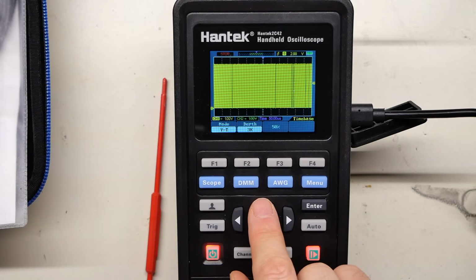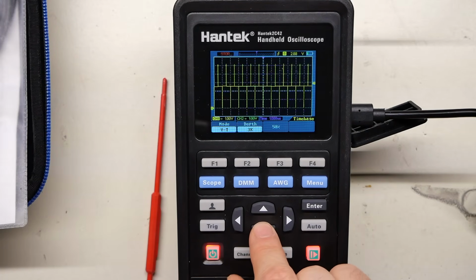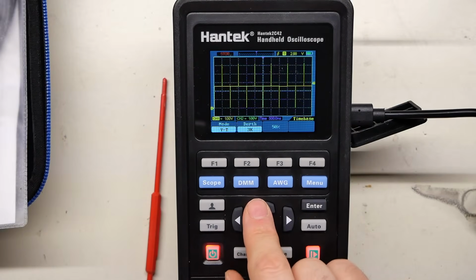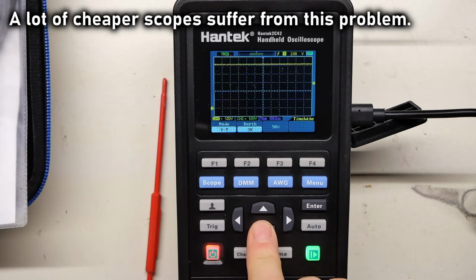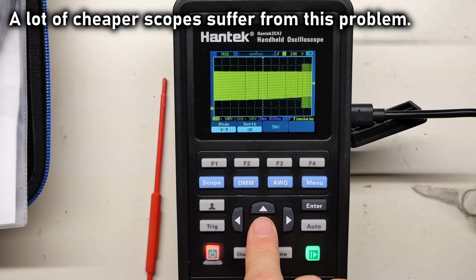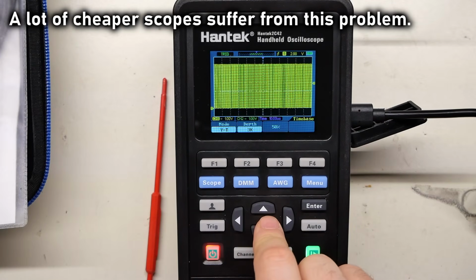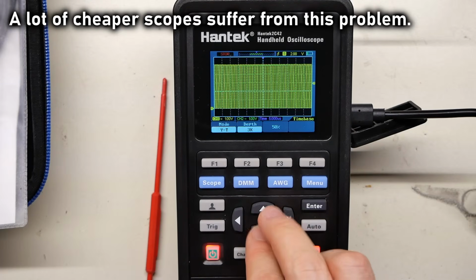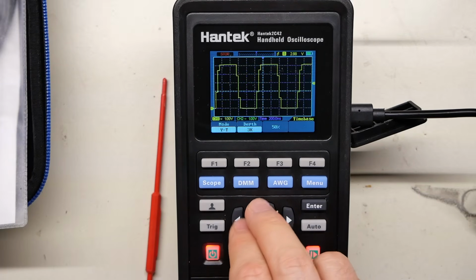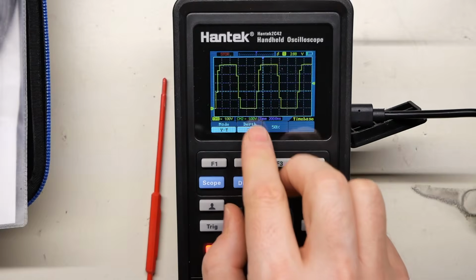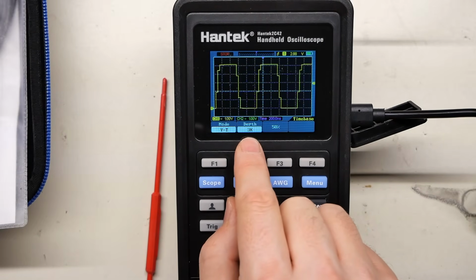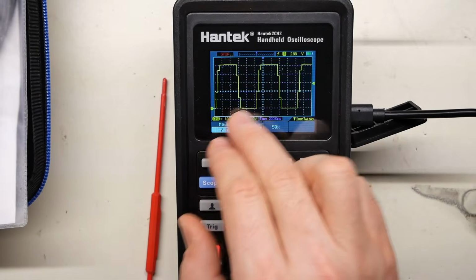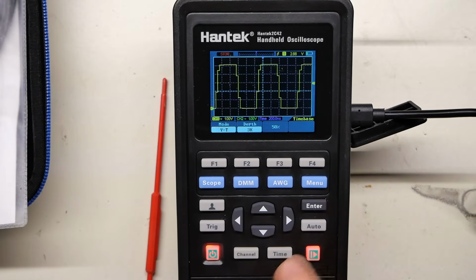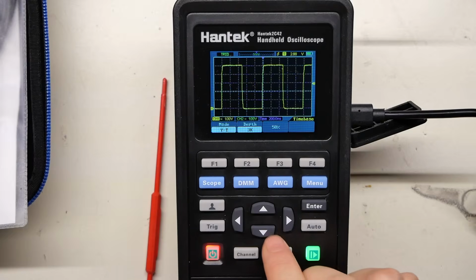Now, if we pause and we zoom in on that, we're going to see something that looks like a signal, but it's not able to really capture enough data. But if we keep going down, down, down, now we're starting to see something that looks like a waveform. Now I paused it. Now look, there it is. Now it's very low resolution because it was sampling only 3,000 points, and it's doing that across the entire buffer. So when we zoom in on that, we got a bit of a mess. But if we hit play now, there it is.